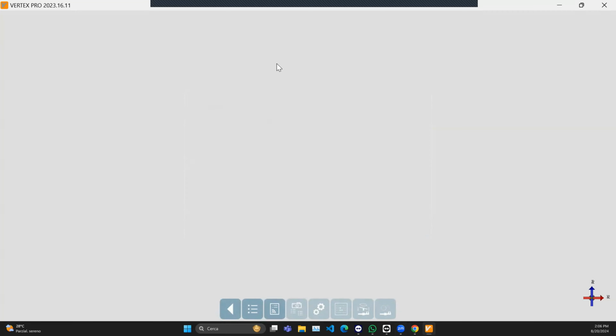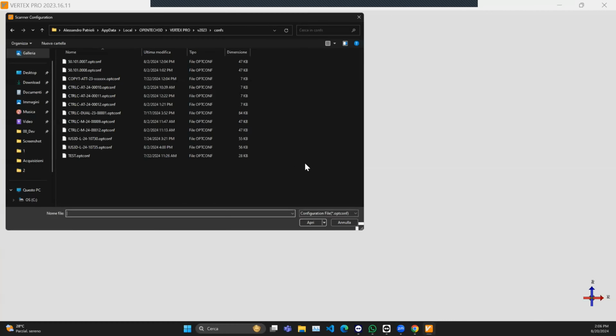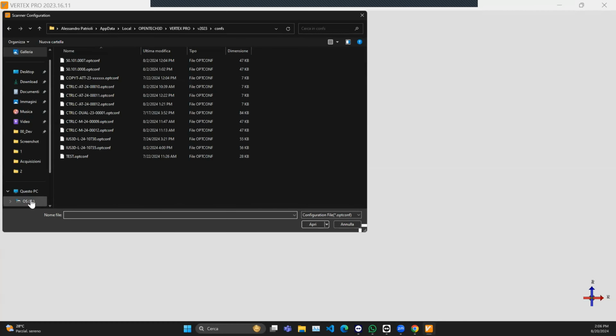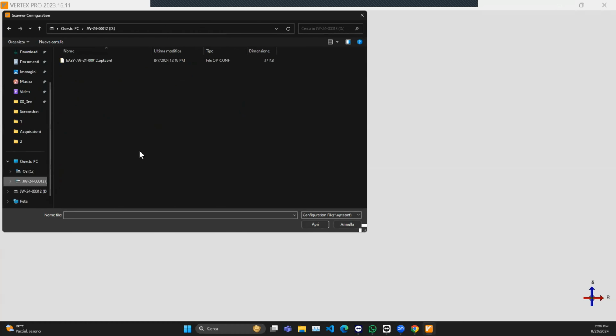With this software, the first time when we start the software on a new computer, we have to load the configuration file for the scanner if we want the scanner to connect to the software, okay? So we click here. This file is an XML, an OPT-conf file stored inside the memory coming with the scanner, the same one where you find the installers.